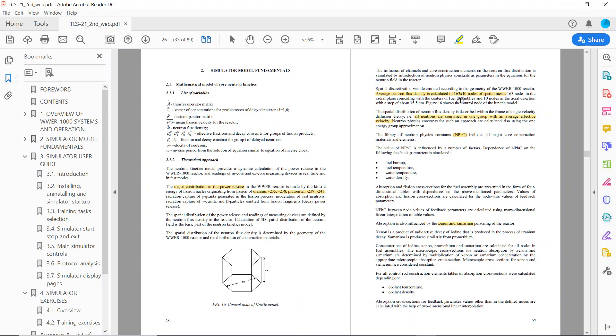It would need a numerical model just to compute the chain reaction and neutron interactions within the fuel rod, but we're just homogenizing this and using a single material point for each fuel element. Even if this is not very refined, it can be fine if we have data from a real reactor. With coefficients calibrated using real operational data, this can be very close to reality. This is totally fine for a simulator used for reactor operation. However, if you were designing this reactor in the 70s and wanted to know the heat production, this model would be very limited.